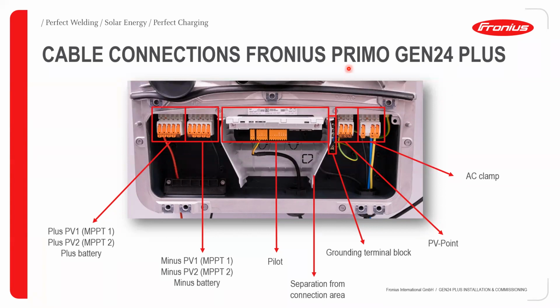Obviously, this is for a single phase inverter. If it were a three-phase inverter, you would have five terminals here: line 1, line 2, line 3, and then neutral and ground. The terminal here is for PV Point. So just for summary, the PV Point is a point where you can actually have power generated for your use, even without a battery. So long as there is irradiation from the sun, you can of course get power supplied on this terminal using our Gen24 Plus inverter. I'm going to be, like I said, talking more on that subsequently.